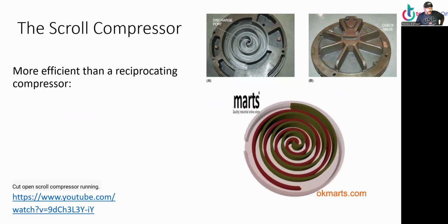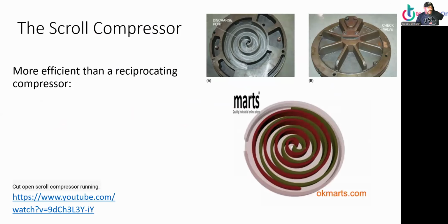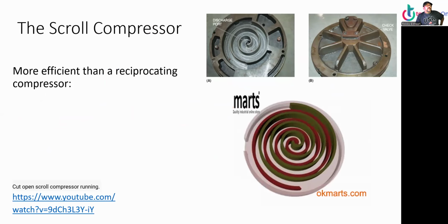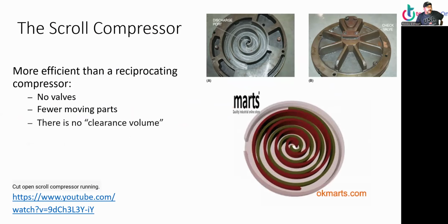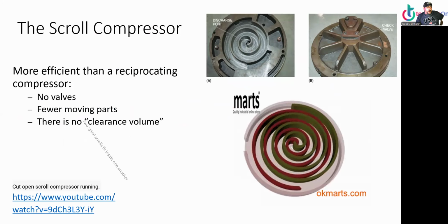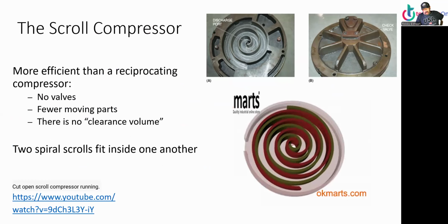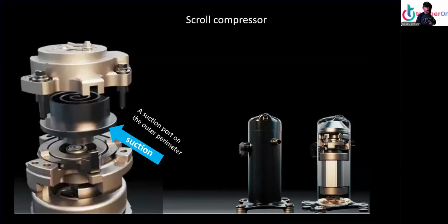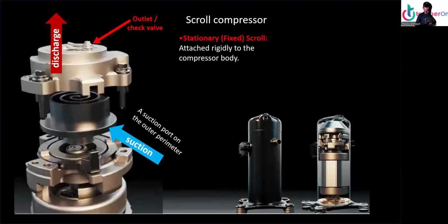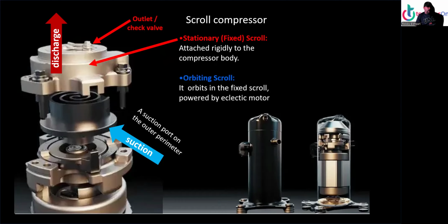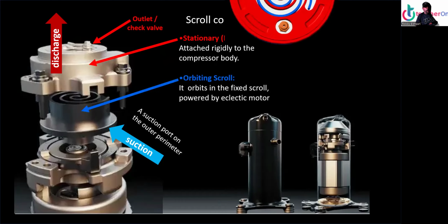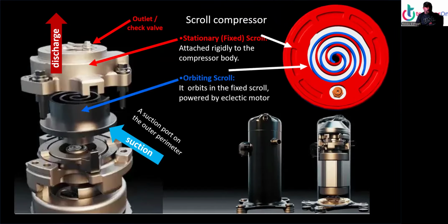Scroll compressor. Now let's move on to the scroll compressor. More efficient than the reciprocating compressor. No valves, fewer moving parts. There's no clearance volume. Two spiral scrolls fit inside one another. All right, suction port, discharge outlet, discharge valve. A stationary fixed scroll is attached to the body of the compressor, and the orbiting scroll is powered by an electric motor. And there's the scroll. All righty. The blue one is the one that moves around. The red one is the fixed.